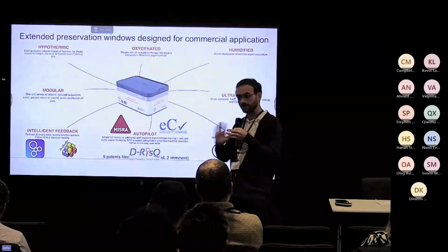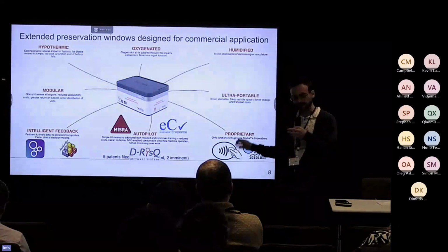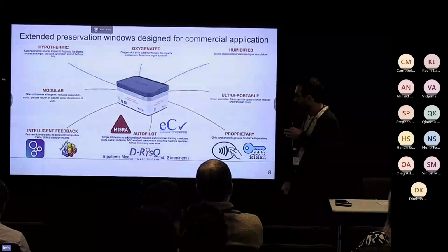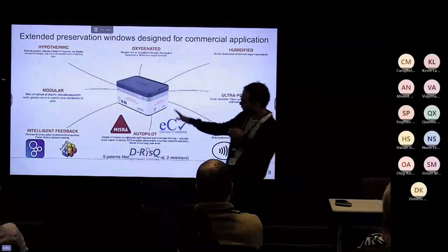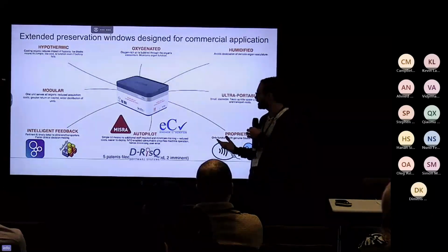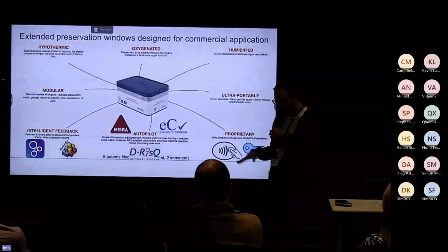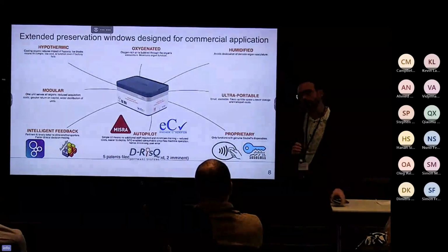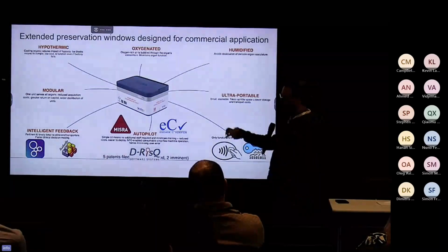Okay? So the machine is extraordinarily simple to use for that reason, but then at the same time secure to use by design. Same technologies used by wave and pay protocols. And no medical device has that kind of thing yet. And yeah, the control system itself was also developed using verification in mind, where we are MISRA compliant and we've done some code level C verification on the device drivers. And at the moment for the industrialization time, we are partnering up with a company called D-RisQ that does autonomous systems development, and it's their first medical device. We've got a few patents on this.